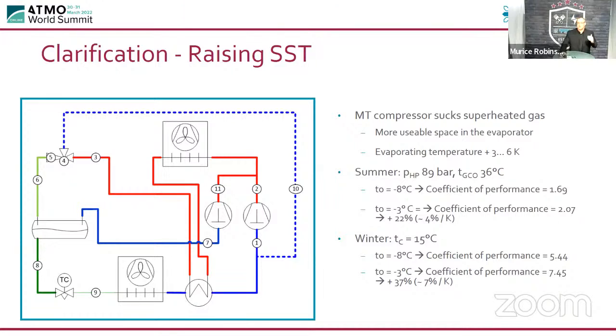In the winter, when we have non-transcritical conditions, in subcritical, if we have the same conditions at -8, the COP is 5.4, and at -3, it jumps up to 7.45. So you have a 37% increase then. So depending on winter and summer, you're still saving around 20%. You do save a little bit more, but the constant is always there.